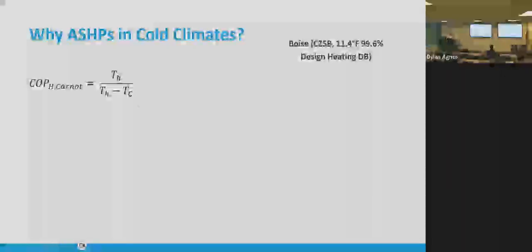Carnot efficiency determines the maximum efficiency of a refrigeration cycle. It's determined by the high temperature source divided by the difference between the high temperature and low temperature source. So the lower the cold temperature source, the bigger this difference and the harder it is to have a good theoretical efficiency. We know that - makes sense, it's harder to pull heat out of a small space or a cold space.